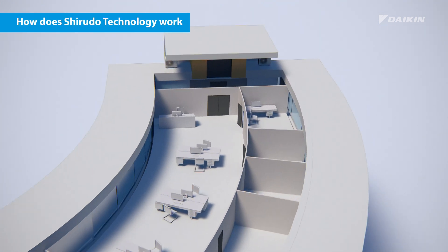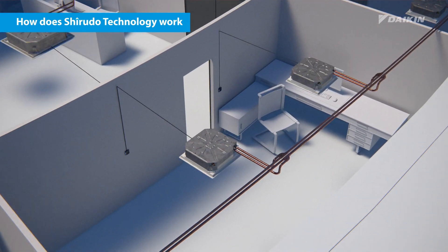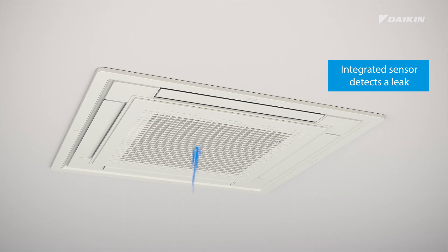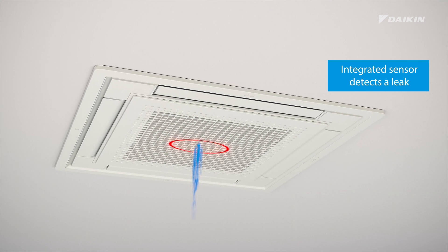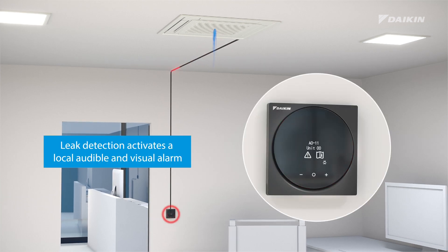How does Shirudo Technology work? In the unlikely event of a refrigerant leak, the integrated sensors in the indoor unit will immediately detect it. The leak detection sensor then activates a local audible and visual alarm, integrated in the Madoka controller.